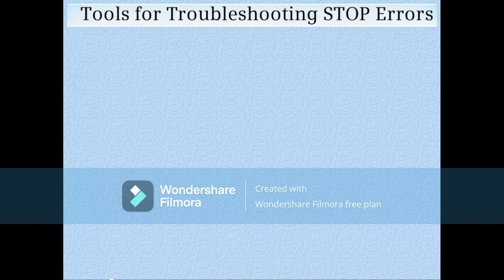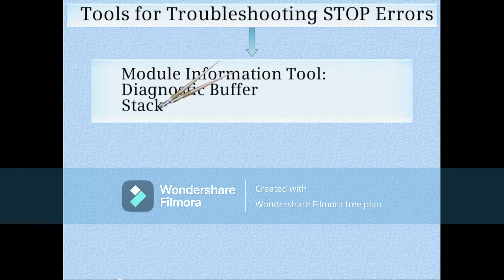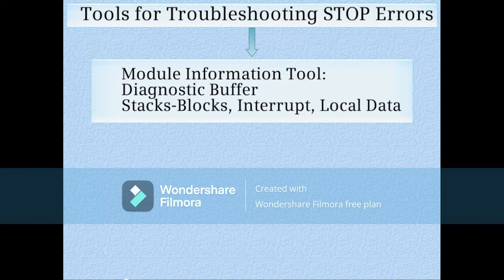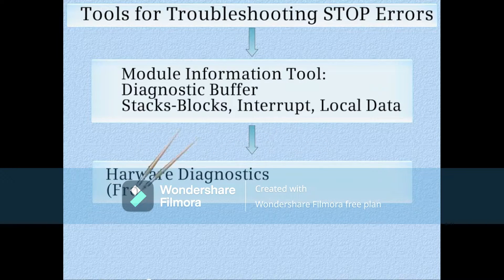Here are the typical tools used for troubleshooting system-detected or stop errors. The module information tool has a diagnostic buffer tab containing diagnostic messages from the CPU, and a stacks tab which gives access to the blocks, interrupt, and local data stacks. You can access hardware diagnostic screens from the PLC menu of SIMATIC Manager and take the hardware configuration editor online for graphical troubleshooting of the hardware system.